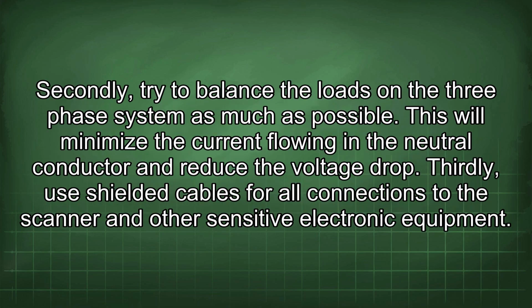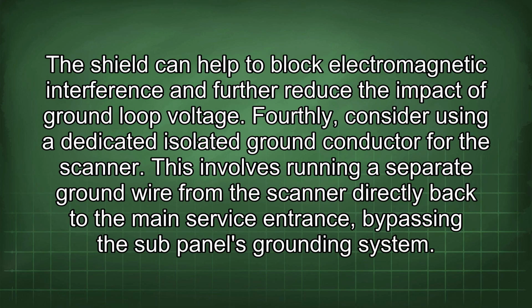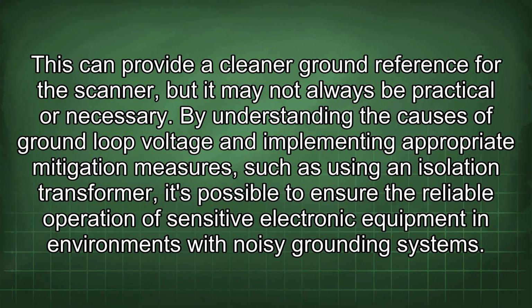Secondly, try to balance the loads on the three-phase system as much as possible. This will minimize the current flowing in the neutral conductor and reduce the voltage drop. Thirdly, use shielded cables for all connections to the scanner and other sensitive electronic equipment. The shields can help to block electromagnetic interference and further reduce the impact of ground loop voltage. Fourthly, consider using a dedicated isolated ground conductor for the scanner. This involves running a separate ground wire from the scanner directly back to the main service entrance, bypassing the sub-panel's grounding system. This can provide a cleaner ground reference for the scanner, but it may not always be practical or necessary.